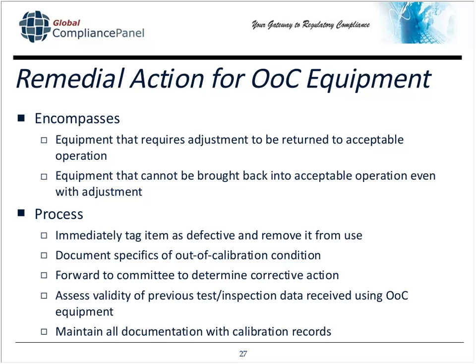You want to forward this to a committee. It's very problematic when you have one person who oversees calibration, who tags the item, who determines the specifics, or in some cases just records something else that's been determined, and then determines the corrective action. This is really better suited for perhaps your non-conforming committee or your material review board.